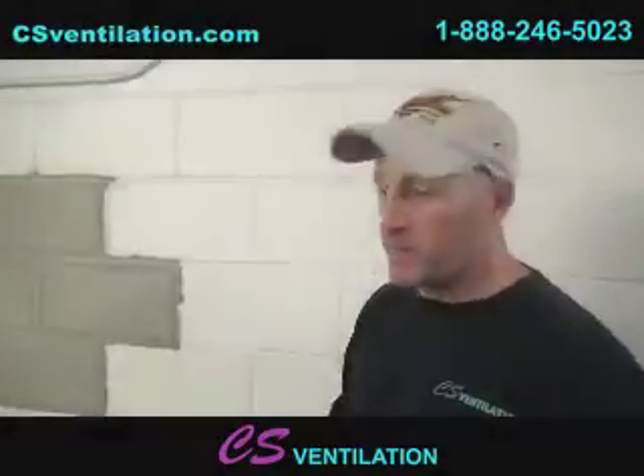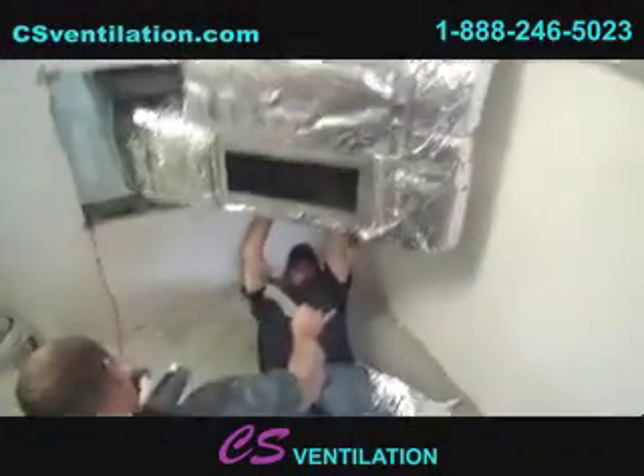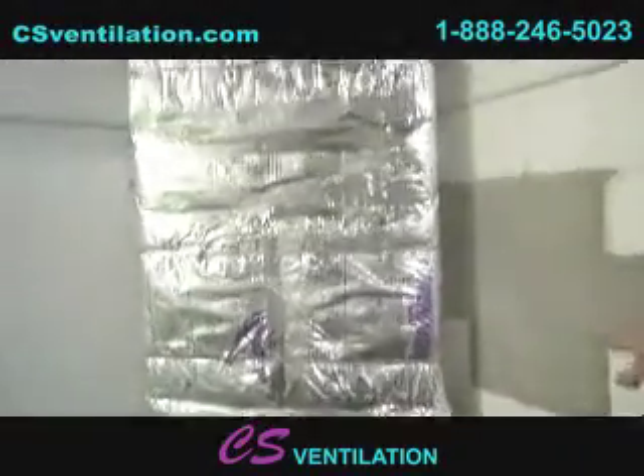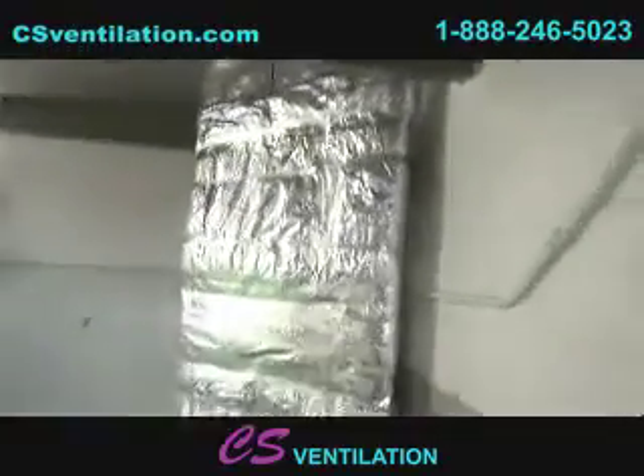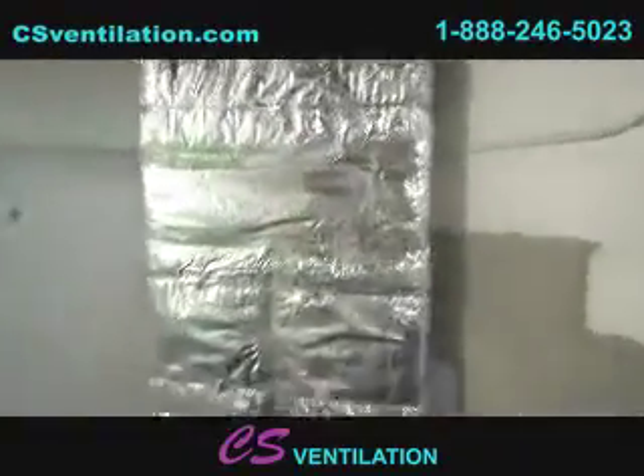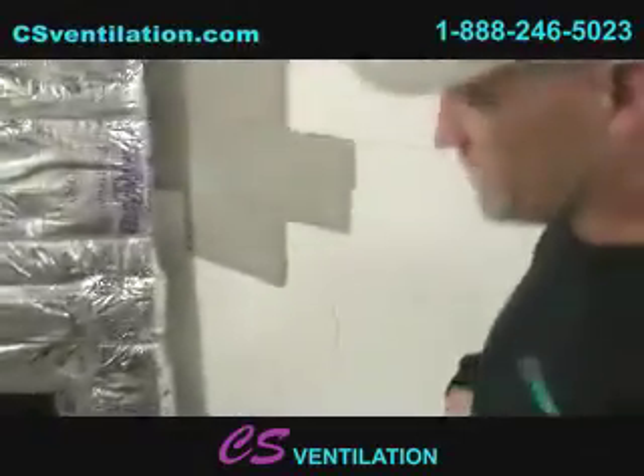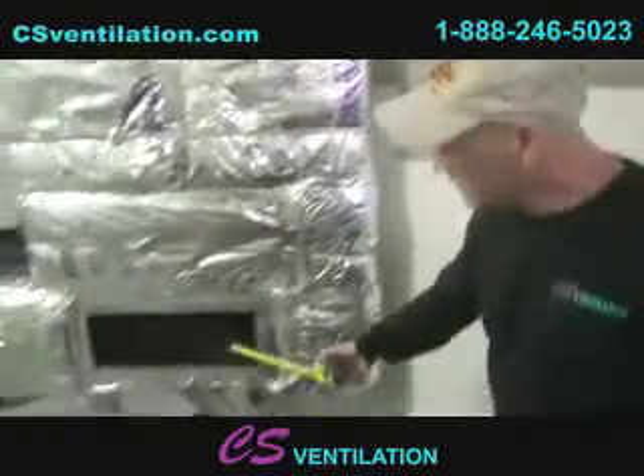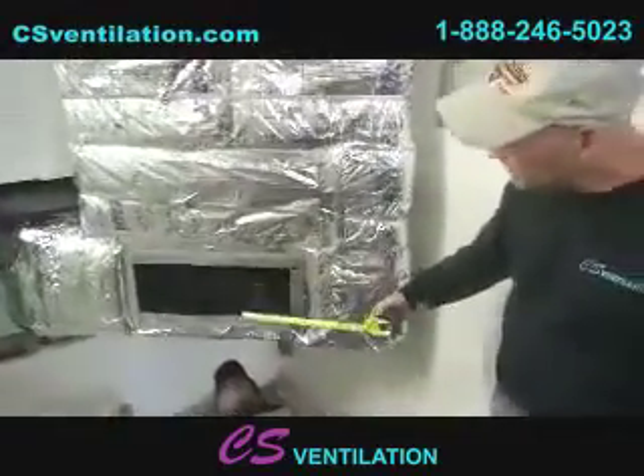We got James and Rob here, putting the last touches on the ductwork as far as wrapping it. This ductwork is triangle shaped, 20 by 27 and 37 inches on the front. The guys have installed an access panel, so for future cleanings you can come in here, open this up and clean all the grease out so it's not a fire hazard.